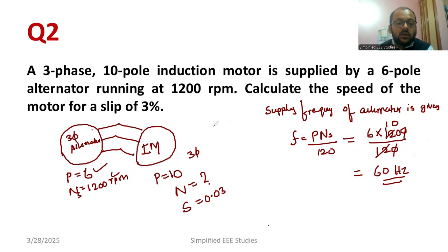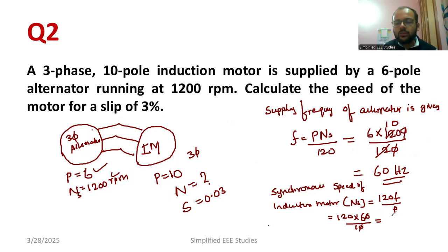Now calculate the synchronous speed of induction motor. That is given by Ns = 120*F/P. Substitute 120*60 divided by 10 poles. This becomes 720 RPM, which is the synchronous speed of the induction motor or speed of rotating magnetic field.